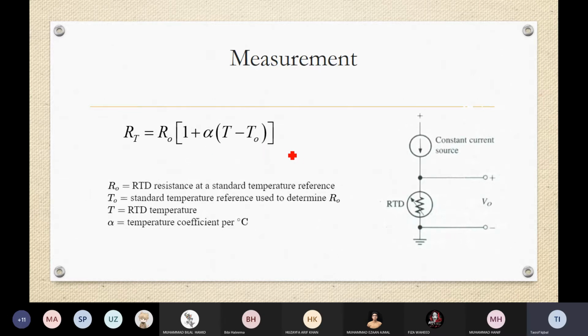So in an RTD, basically we are going to detect the output voltage, and for this we need to have a constant current source. We have already discussed how to generate a constant current source, and that constant current source could be connected in series with the RTD, and therefore we can measure the voltage across the RTD and then detect the temperature. We can detect the resistance and directly detect the temperature.